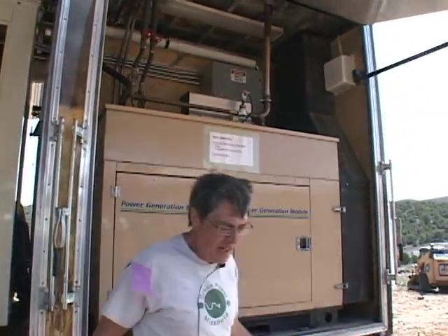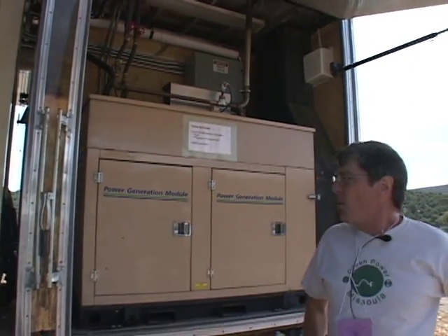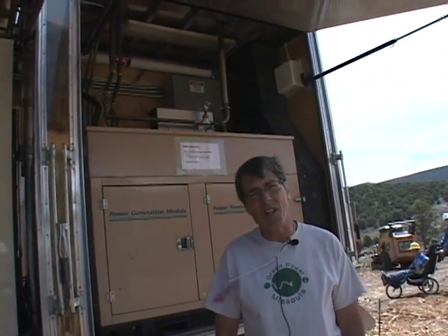And then here is mostly an off-the-shelf gen set. We're using a Chevy V6 that can run on propane or gasoline and producer gas. It's been modified. And I'll show you the engine side, and then we have it attached to a generator. This system produces 25 kilowatts of electricity, and I'm recovering about 200,000 BTUs per hour of waste heat.